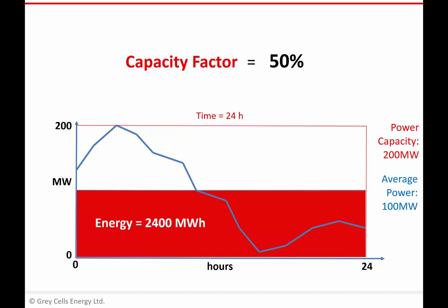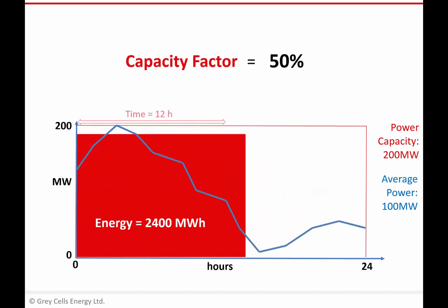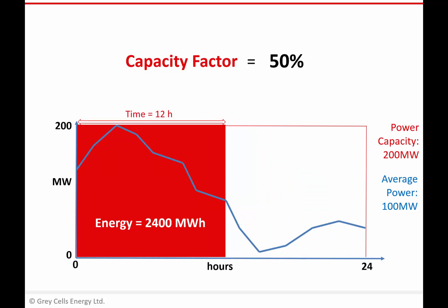Another way of thinking about this chart: how many hours would we need to operate the plant at its maximum capacity of 200 megawatts to produce that same 2400 megawatt hours of actual energy? The answer is 12 hours. So we could operate at 200 megawatts for just 12 hours rather than at 100 megawatts for 24 hours. The capacity factor can therefore also be expressed as 12 hours divided by 24 hours. These 12 hours are what we call full load hours — the equivalent number of hours the plant would need to run at maximum capacity to produce the actual energy output.